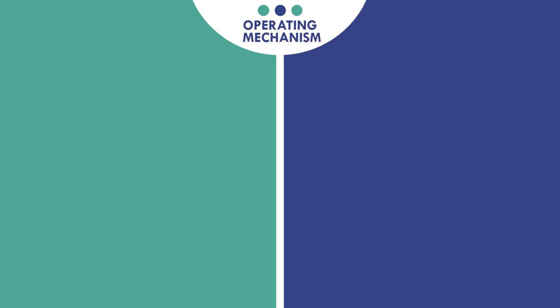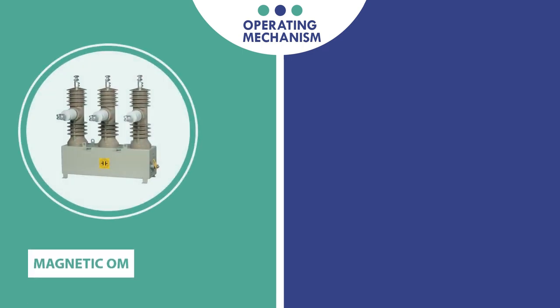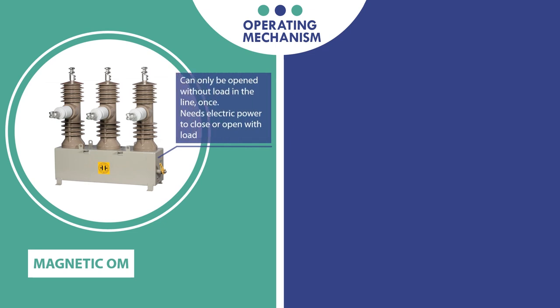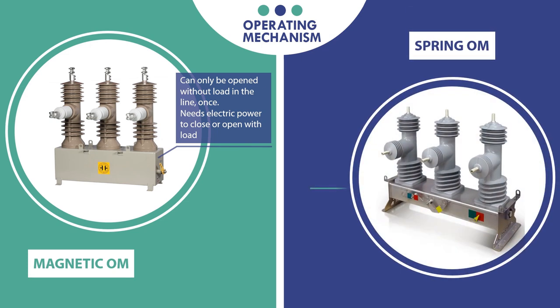Let's move to the third factor in choosing a right recloser: operating mechanism. Here we have two main types: magnetic and spring operating mechanisms. In general, magnetic operating mechanism can only be opened without load in the line. Also, it needs electrical power to close or open with load. For spring operating mechanism, you can perform trip-close-trip under full load in your line and it can be operated and manually recharged.